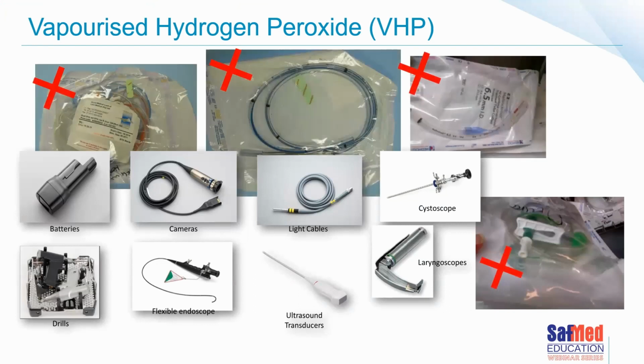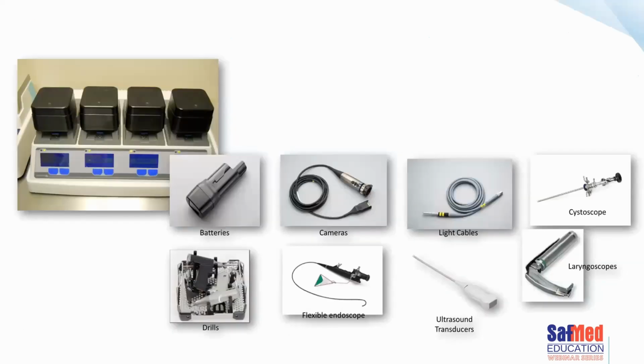Here are some images of the things that we tend to process in South Africa in our low temperature sterilizers. That's not what they were designed for. We often use low temperature sterilization for things we opened in error and we're going to re-sterilize, or something that's expired and we want to try and re-sterilize to keep it going. And that's what we end up doing. That's obviously not the ideal thing. It's not what these devices were designed for.